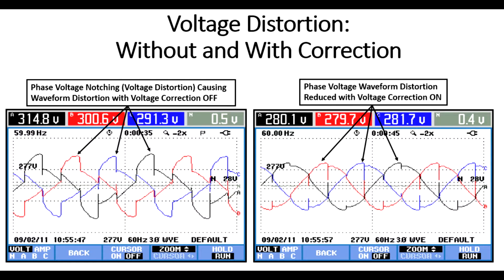We had from 315 to 291 volts. There was quite a difference of voltage there, quite an unbalance or imbalance. On the right, we're showing them within a volt or two. So we can see on the left graphic here the notching that was causing a significant amount of problem. It caused the motor and its drive, and in fact the power transformer feeding it, to moan and groan as the machine would physically cycle and operate.